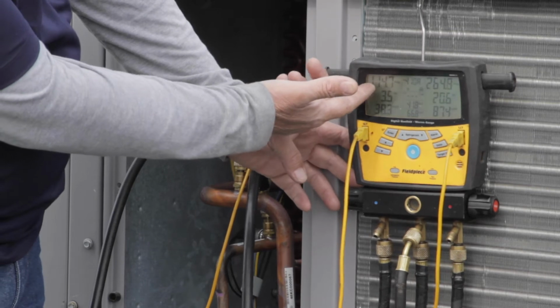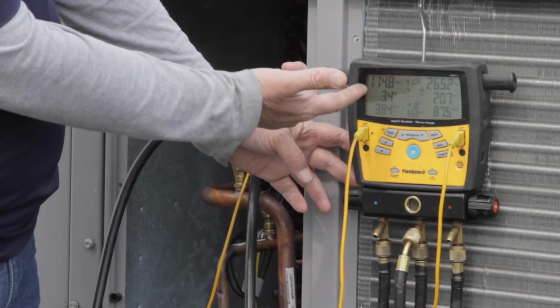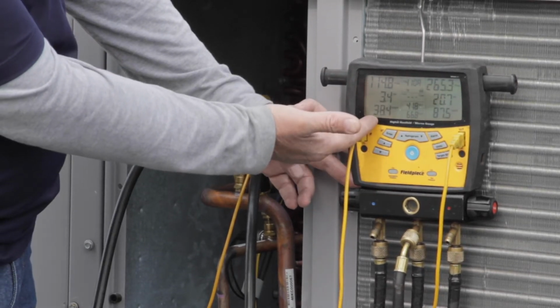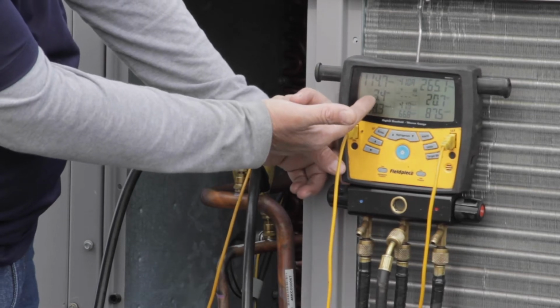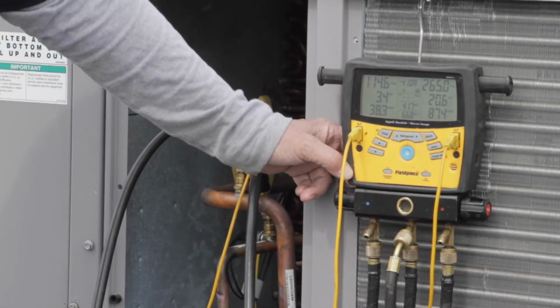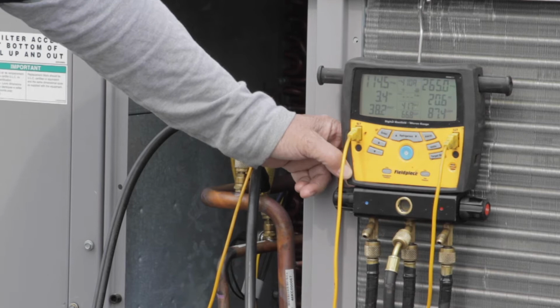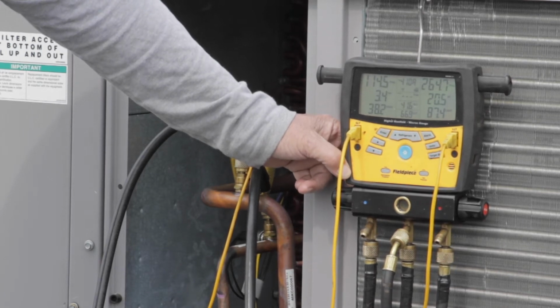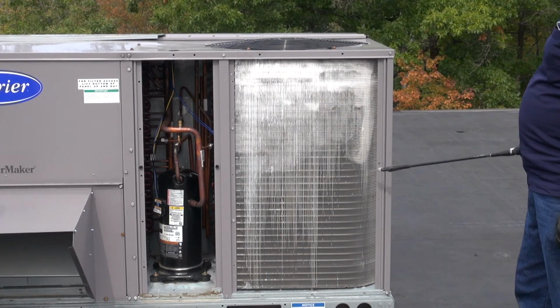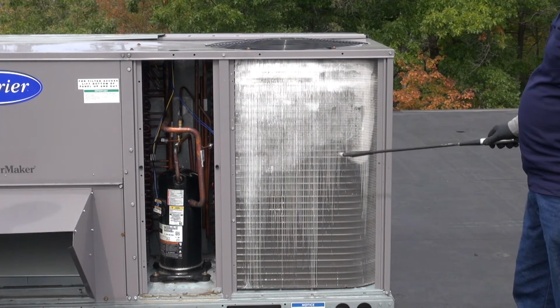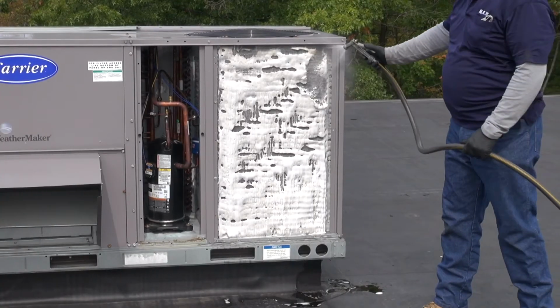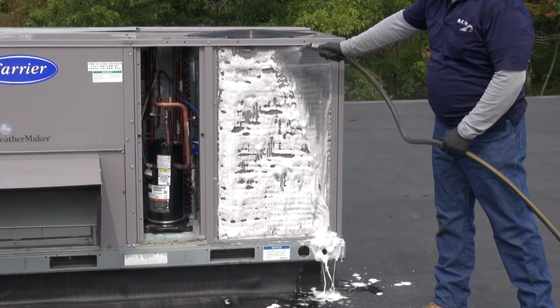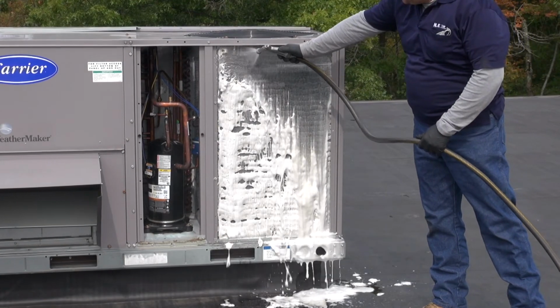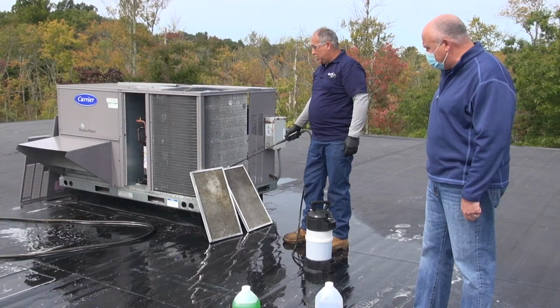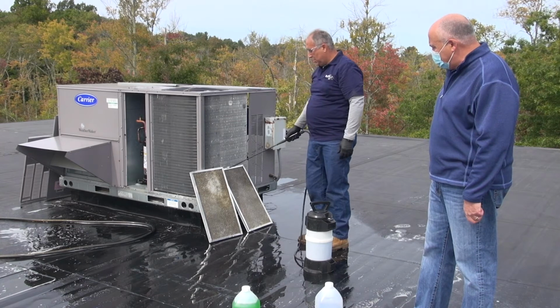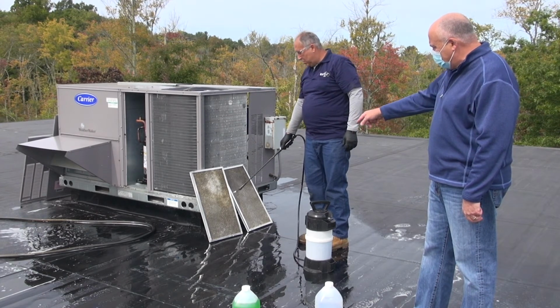If refrigerant is needed, it would be added to the unit at this time. If refrigerant levels are low, it can indicate a leak, which would need to be fixed before it causes damage to the unit, requiring a major repair. The condenser coils are cleaned with a chemical cleaner to wash away any dirt and pollen from the coils. The economizer screens are also cleaned, or they can be replaced every few years.